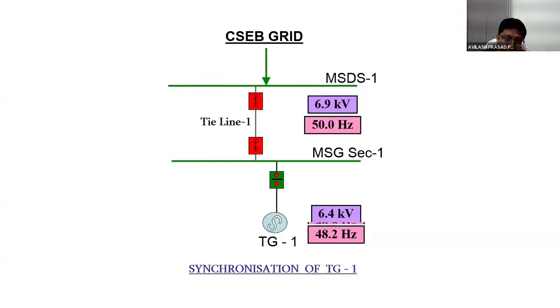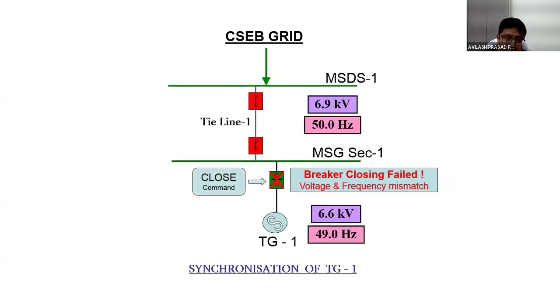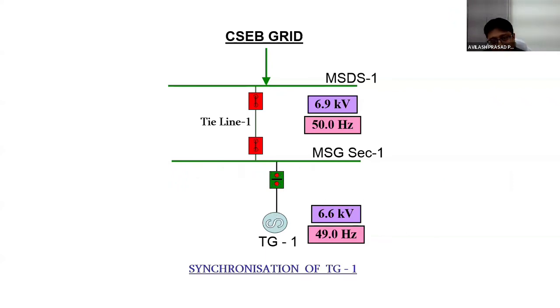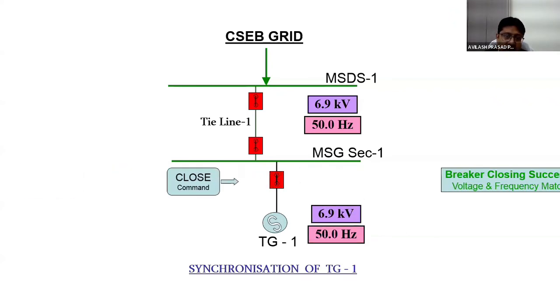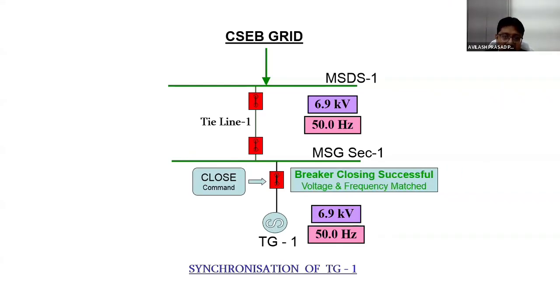And if we try at 6.6 kV and want to synchronize it by giving the close command, it will not synchronize, as the voltage of the grid is 6.9. Then we have to again increase the excitation and hence the voltage to 6.9. And if we give the command, then it will connect the tie line and we will connect it with the grid. This is the synchronization of turbo generator TG1.